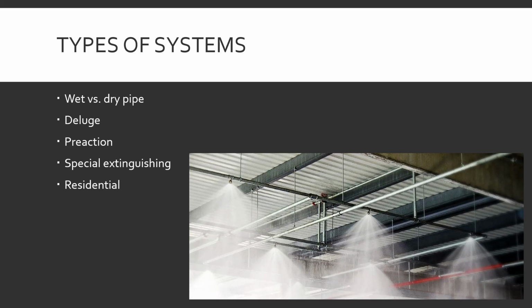So we're going to use a real fire, for example. Sprinkler head breaks. Okay, that's one. Nothing's happening yet. And one of our earlier detectors, let's say a rate of rise detector, goes off. That's our two things. All right, now the system goes, I have two things telling me there's a fire. Pretty good chance it's a fire. All right, I'll let water into the system, and then water will start to come out of the sprinklers. Now, those two things could be anything. It could be a sprinkler head going off. It could be a sprinkler head and a fire alarm pull station on a wall, or it could be a smoke detector and a pull station. It just takes two inputs from the system to tell it to put water into the system.